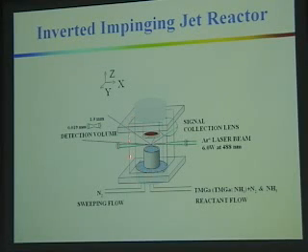What this is, is a set of quartz flats. We have a laser beam that will come in and focus down to a 30 by 30 by 300 micron region. And then we'll look at the 90-degree scattered light from that. And that will give us a signature for the molecule by looking at the vibrational or possibly the electronic spectra, Raman spectra of the molecules in that volume.